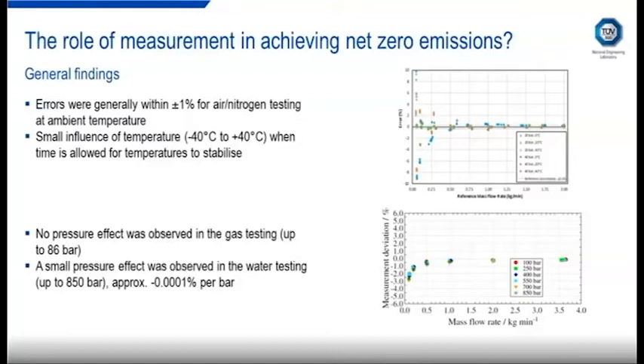The effect of pressure is shown on the graph at the bottom. So this shows a pressure range from 100 to 850 bar. And you can see the effect of pressure isn't really perceivable, it's very small. So we didn't really see a pressure effect in testing with gases up to 86 bar, and in the liquid tests with water up to 850 bar, the effect was estimated at 0.0001% per bar. So that's quite insignificant compared to the kind of uncertainties that we have to achieve at hydrogen refueling stations.